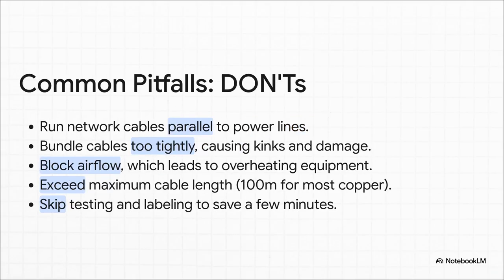And here's the other side of that coin, the big don'ts. These are the classic mistakes that lead directly to failure. Don't run data cables parallel to power lines. Don't bundle them up so tight you crush them. Don't block airflow and let your equipment cook. Don't stretch a copper cable past its 100-meter limit. And the biggest one of all, don't get lazy and skip testing and labeling just to save 5 minutes. It will cost you hours down the road, guaranteed.